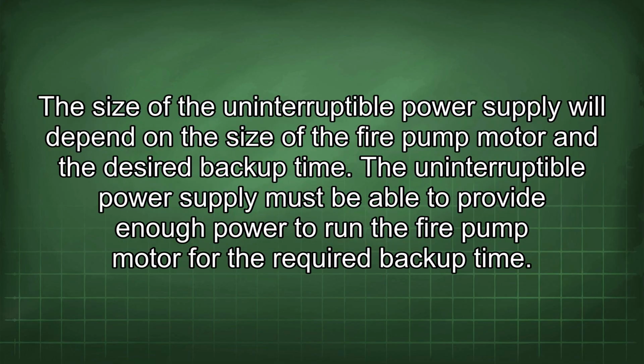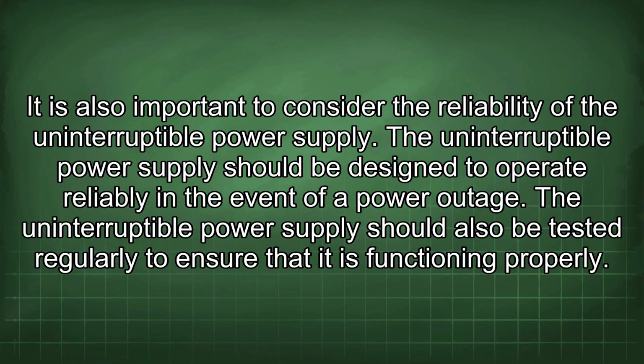The size of the uninterruptible power supply will depend on the size of the fire pump motor and the desired backup time. The uninterruptible power supply must be able to provide enough power to run the fire pump motor for the required backup time. It is also important to consider the reliability of the uninterruptible power supply. The uninterruptible power supply should be designed to operate reliably in the event of a power outage. The uninterruptible power supply should also be tested regularly to ensure that it is functioning properly.